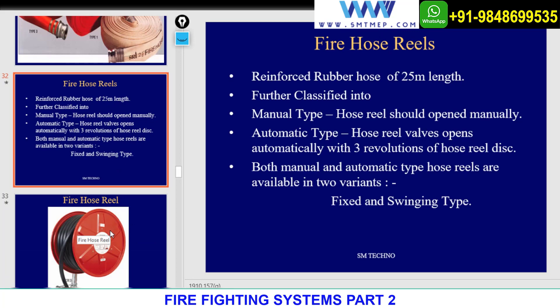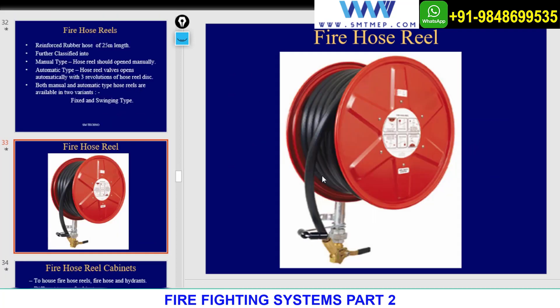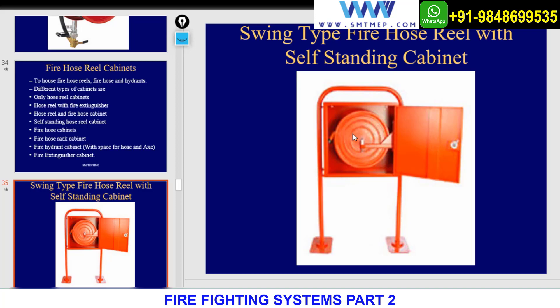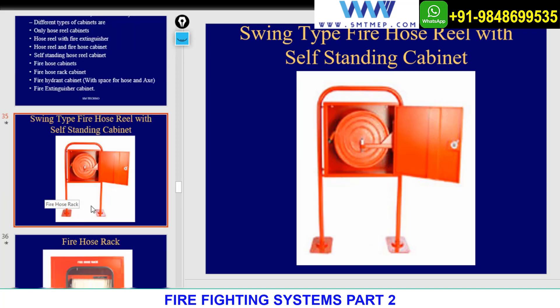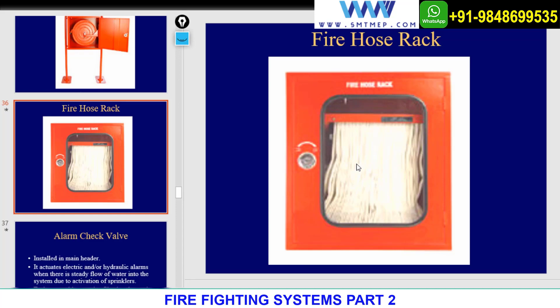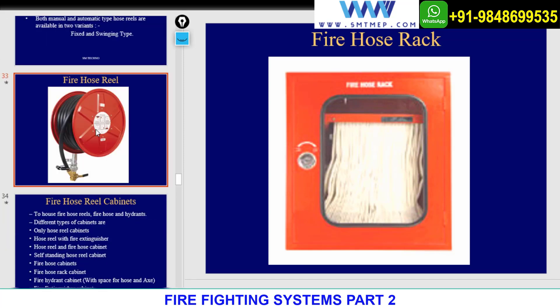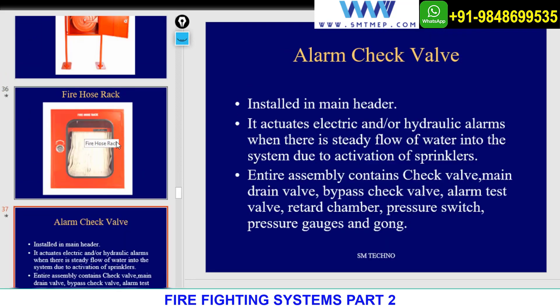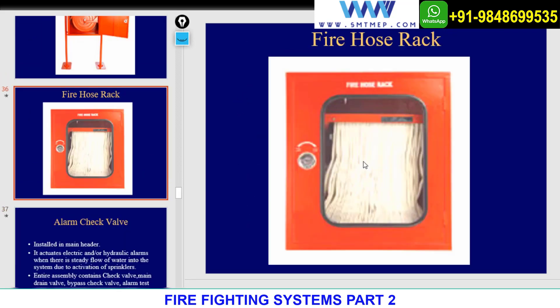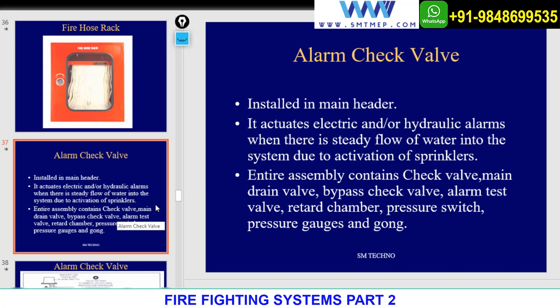The hose reel is also a hose pipe but of the non-collapsible rubber type, and it includes a nozzle. The red color hose reel placed in a box is called a hose reel cabinet. Another option is the hose rack, which is applicable only for collapsible hose pipe — not non-collapsible — because the hose needs to be arranged in a specific manner so that during a fire it can be easily pulled out.